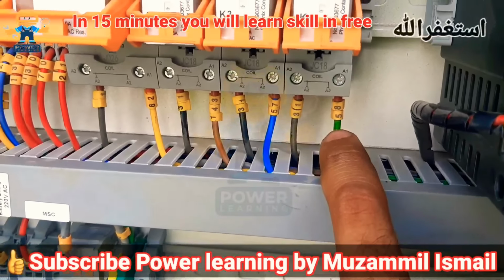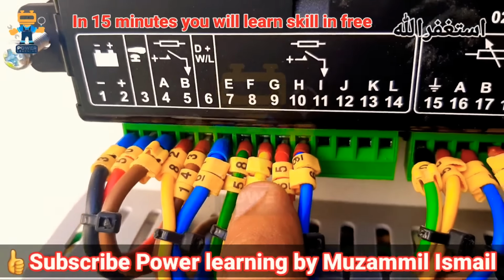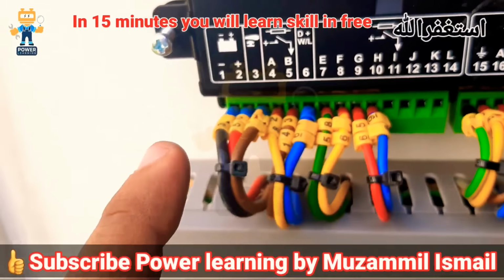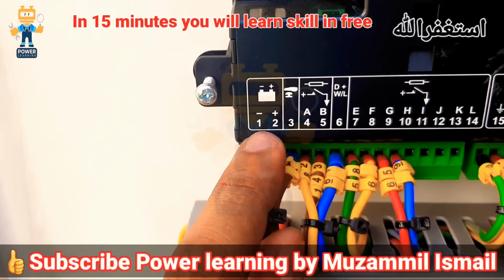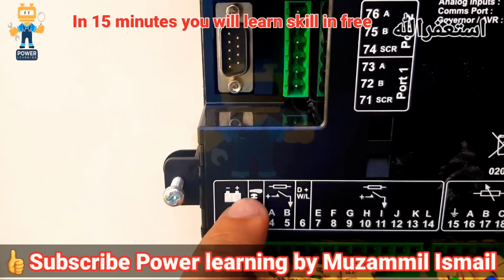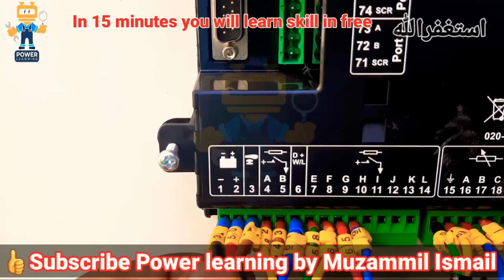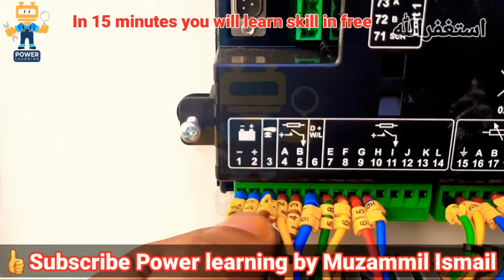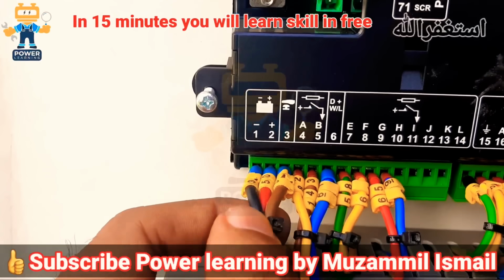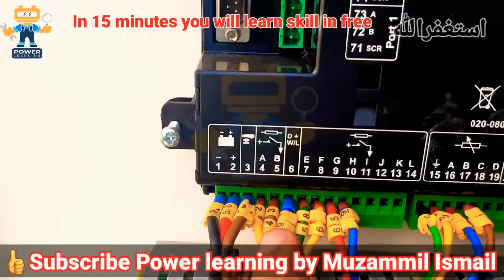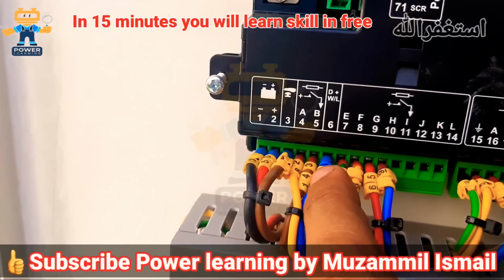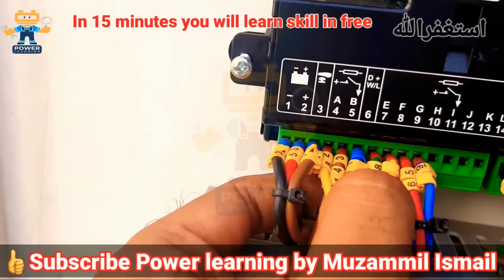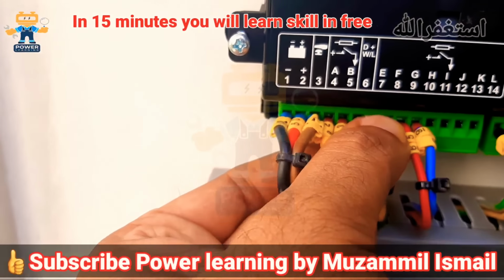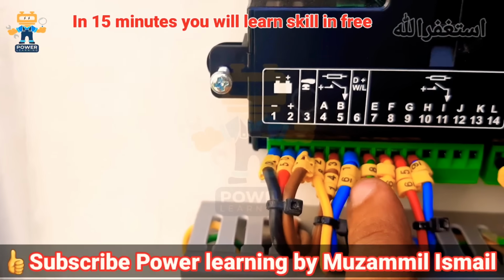So after that we have 58 alarm for common alarm relay 58. So here this 58 is connected here. If you see, this is connected here, 58 from digital output. So as you see, number 1 is main negative, battery negative, and battery symbol is there, and positive from battery. So this is the power supply of the controller. Number 3 is from the emergency switch. The emergency switch supply will be connected here, and number 4 is the fuel relay, number 5 is the starter relay, and number 6 is from the dynamo. It is sensing the battery voltage, charging or not charging. It will give you a signal here.